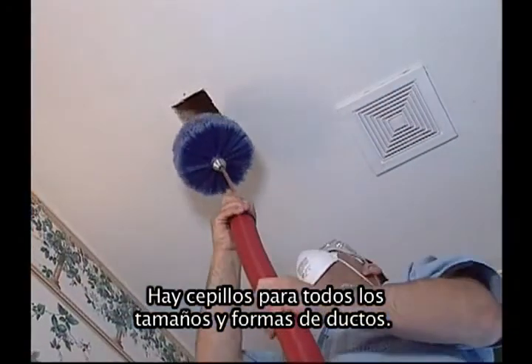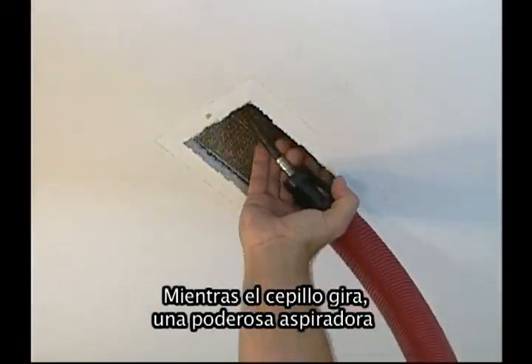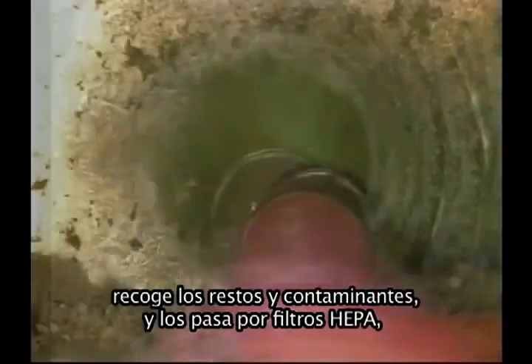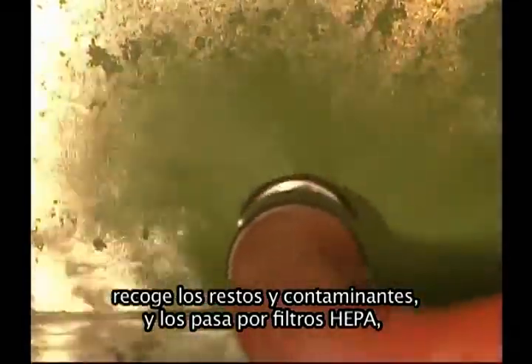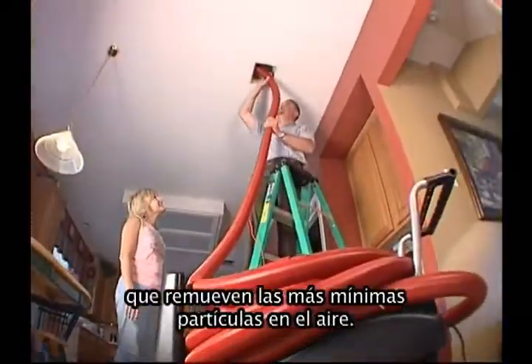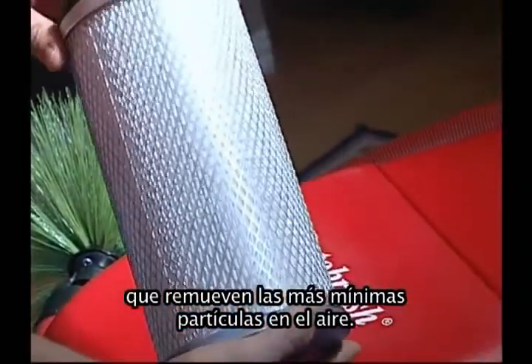The spinning brush makes contact with the surfaces of the air ducts and accommodates all sizes and shapes of ductwork. As the brush spins, a powerful vacuum collects debris and contaminants and scrubs them from the air using HEPA filters, which remove the tiniest airborne particles. The brush is a powerful cleaner, but it's gentle and won't harm your ducts.